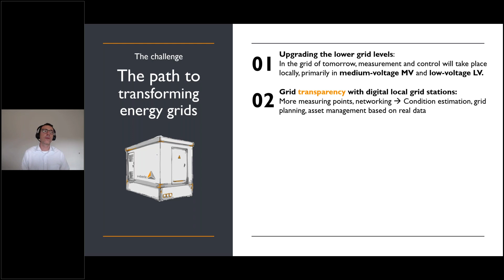What is the path to transforming the energy grids? We have to upgrade the lower grid levels. In the grid of tomorrow, measurement control will take place locally, primarily in medium voltage and low voltage stations. We have to extend the grid transparency with digital grid transformer stations. We have to add more measuring points, and they have to be networked. We have to make a condition estimation, a grid planning, asset management. All these parts of the utilities have to make their decisions on good measures which are coming from the low voltage grid.